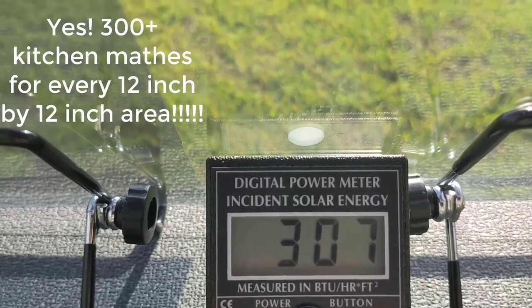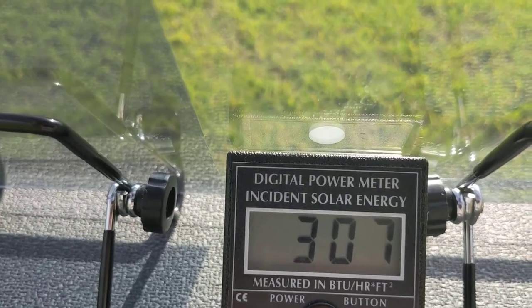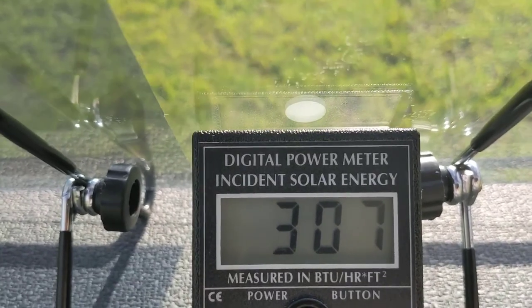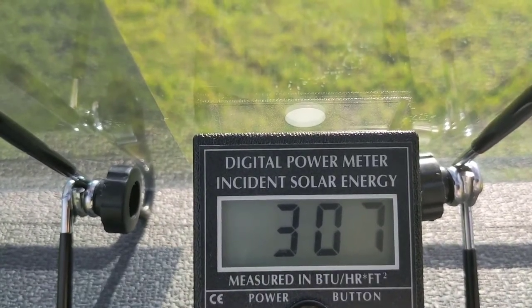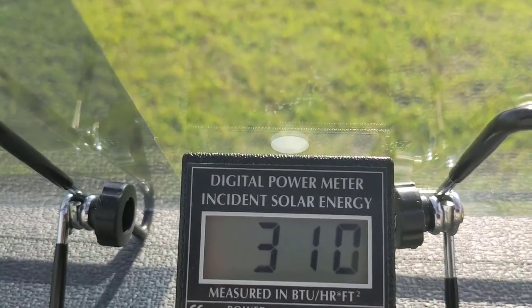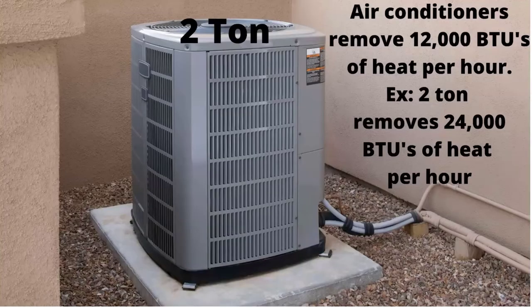Imagine a window that has 10 square feet of glass — you multiply that by 300, that's 3,000 BTUs for every hour that the sun is hitting that glass. If you start adding all your windows, you can see where this affects the cooling load of your air conditioner, which is designed to remove the heat coming into the house in BTUs. We'll get into the BTUs and air conditioning calculation from our computer, but we wanted to show you this first.